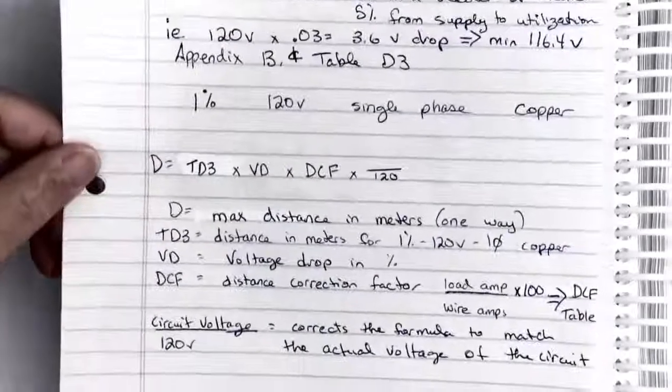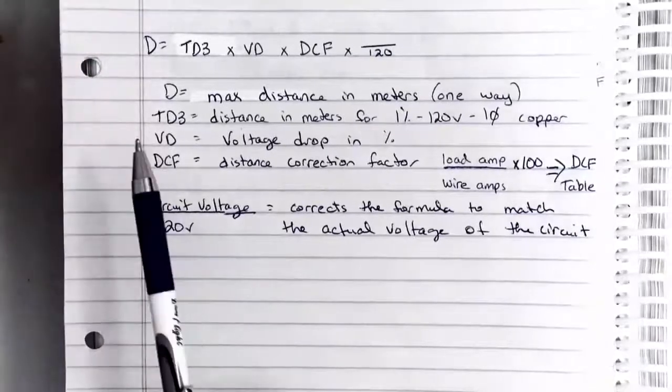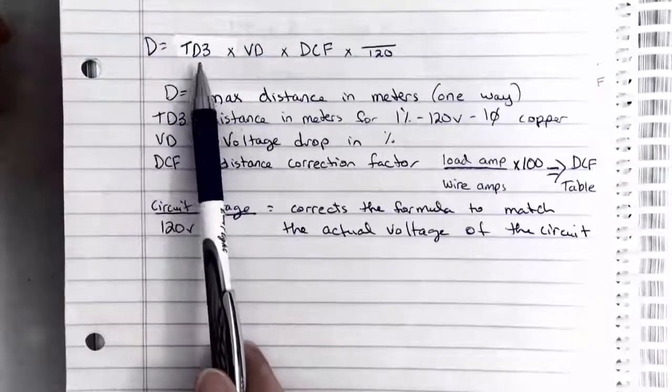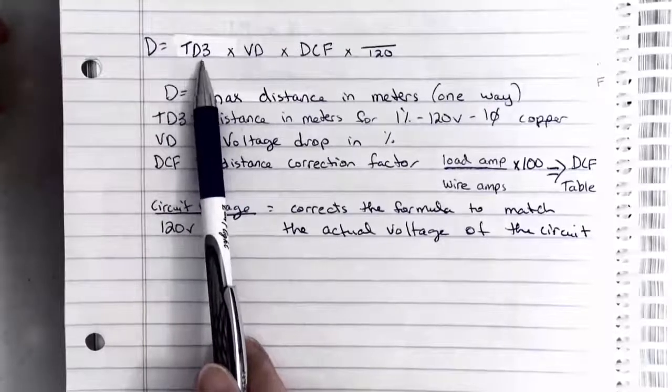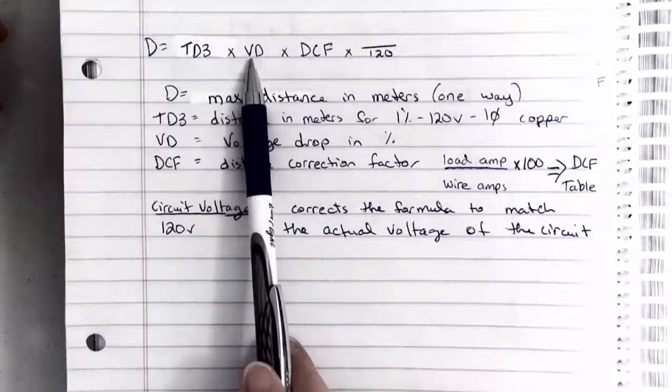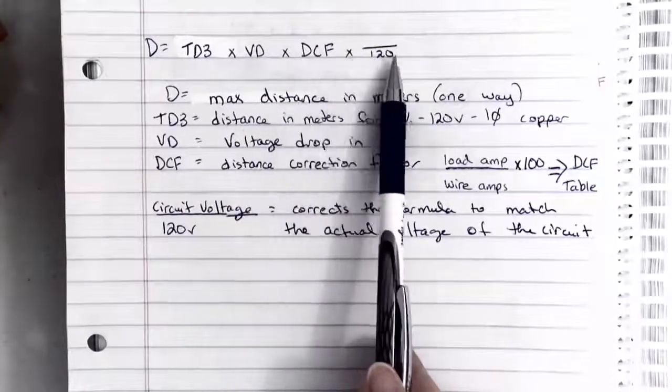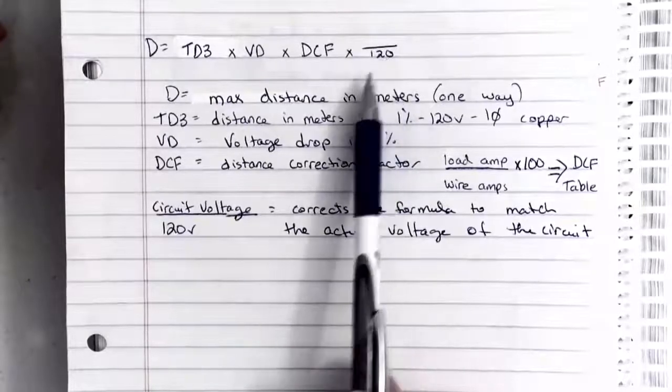So again, if we're looking just at this formula, the distance in meters equals the distance from the table in meters times the voltage drop that we're allowed times the distance correction factor times our actual circuit voltage divided by 120.